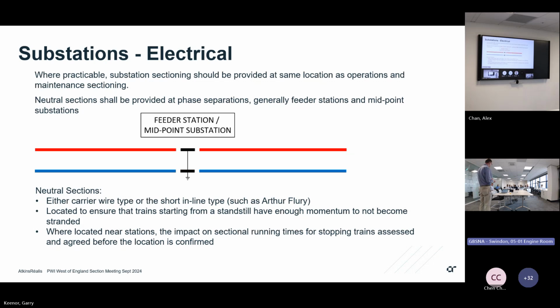We don't, and we have got examples on the network where you've got a substation with a neutral section, and then half a mile away, we've got an insulated overlap with sectioning. That's wasteful. If you can avoid doing that, merge them, common them up, make sure that the isolation limits are aligned with your substations.